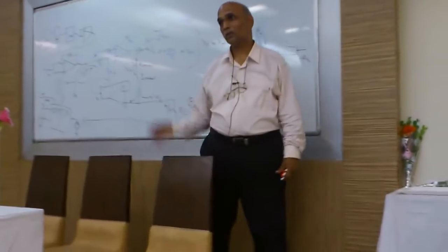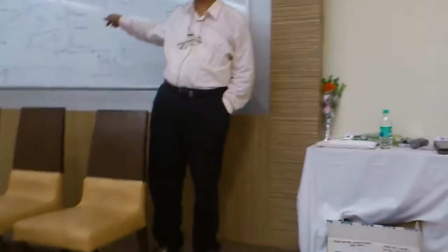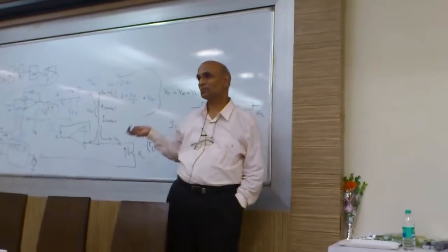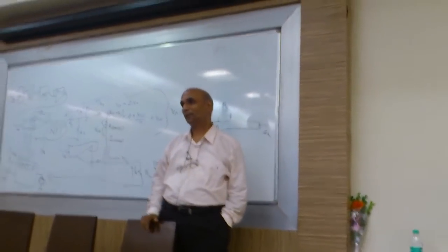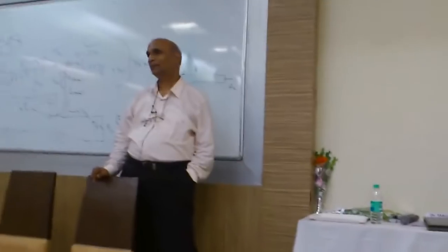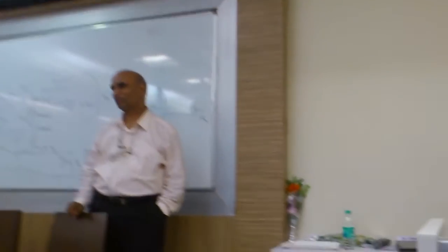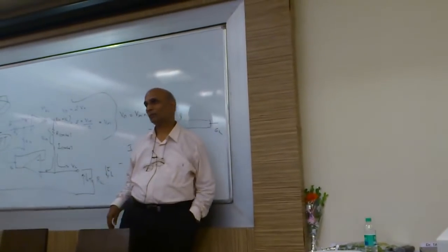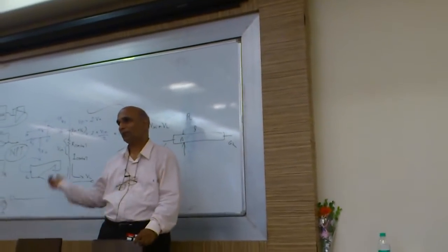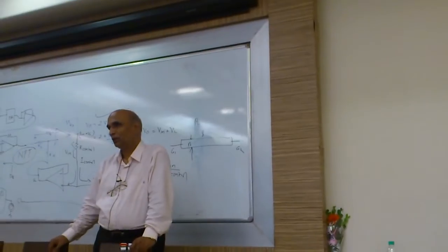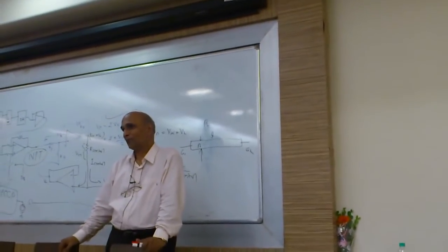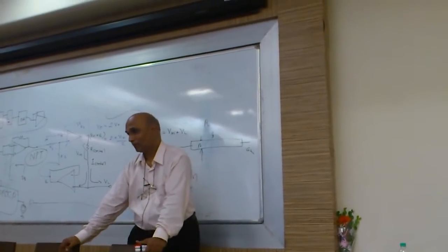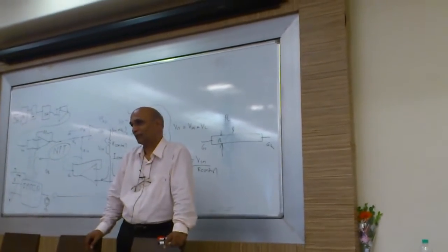Coming back to ISO 13485, if I'm supposed to design this instrument, I have to document the procedure which I use for designing it. I have to give the maintenance procedure, and I have to give the software. If I'm using software, the software has to be validated. And I must write down who was the person who did the software and what typical algorithm he has used. Instrument design was easy a very long time back, but today with ISO 13485, you have to document the software, and it takes more time to document software than to develop it. So you have to be serious about ISO 13485.